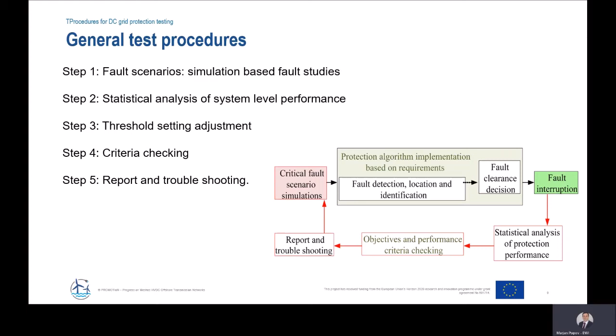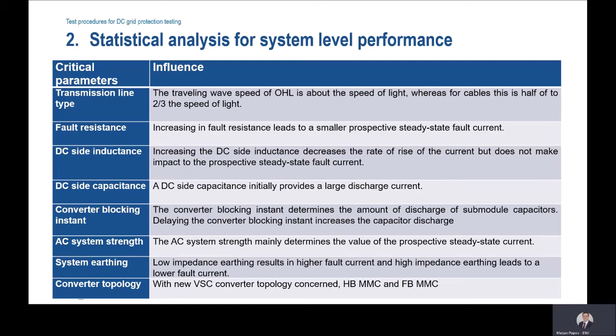Regarding the statistical analysis for system level performance, again here we have numerous parameters that we have chosen and which are important to vary in order to see not only the performance of the protection but also the performance of the system and the associated components within the HVDC system. These are transmission line type, fault resistance, DC side inductances and capacitances, converter blocking instant, AC system strength, system earthing, and converter topology.